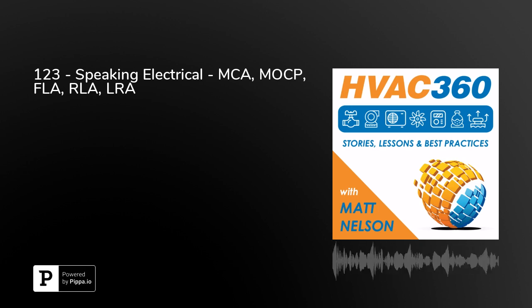All right, so now comes a very important one. Pay attention. Now we have the MCA, which is the minimum circuit ampacity. This is what electrical engineers use to size conductors. Wire, that's a conductor, same thing. But, again, using the right terminology, sizing conductors to prevent overheating under normal conditions. Again, overheating is bad. That leads to fire. Now, the size can be increased, using your experience, if you want to counteract voltage drop, but the size is never smaller than what they specify for that circuit ampacity. So that minimum circuit ampacity sets the size for the conductor.